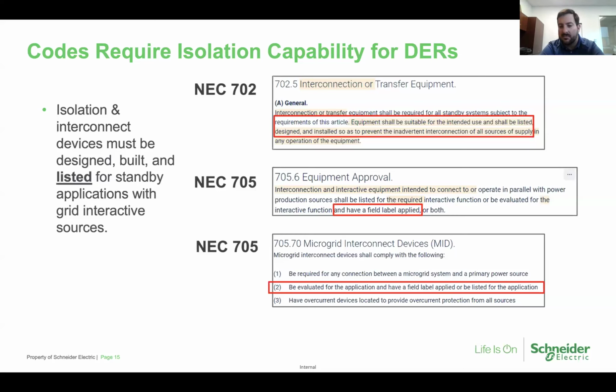And that basically means in most applications, it needs to be UL or similarly listed with one of those agencies to a standard that is specific to the application in which it's being used, which is interconnect applications and resilience applications. You can't just take something and say it's listed to be used as an overcurrent protective device and use it for this application, even though it might have similar functions, because the requirements for the design and qualification of that is different. So it has to be a standard that is specific to the application of interconnection and isolation. And at the end of the day, to most of us, that means a UL label. Next slide.